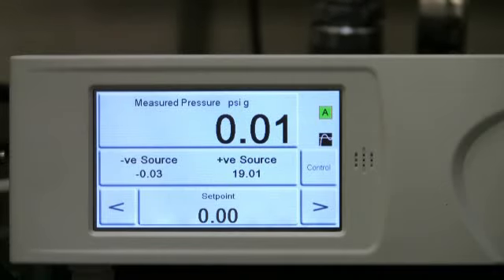We will now adjust the regulator to set the supply pressure to approximately 160 psi. The supply pressure should be set to 10% above the full-scale pressure of the installed control module. For this calibration run, we are only controlling positive pressures. If negative gauge or absolute pressures are required, we would need to connect a vacuum pump to the negative supply port.